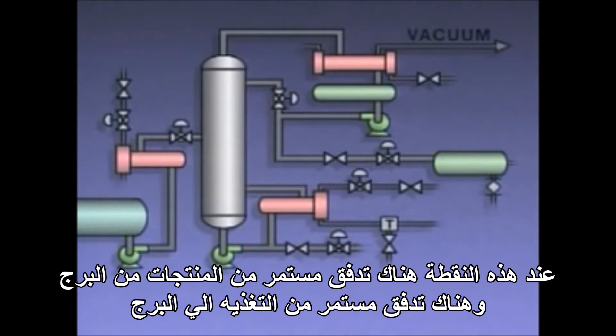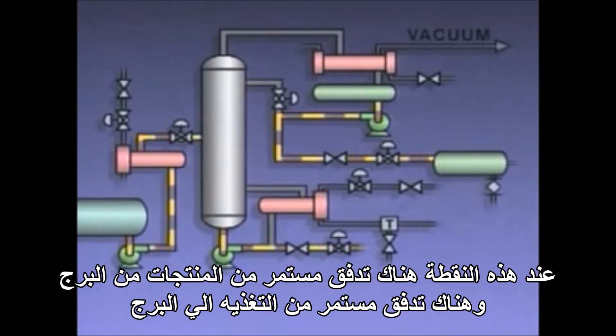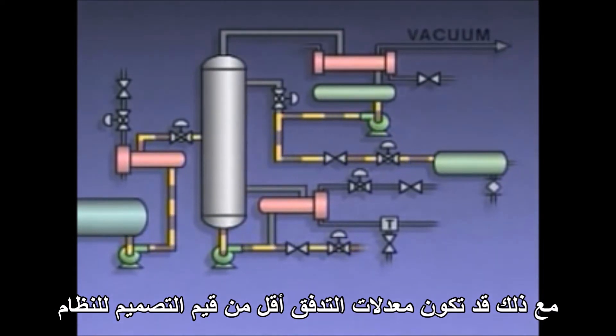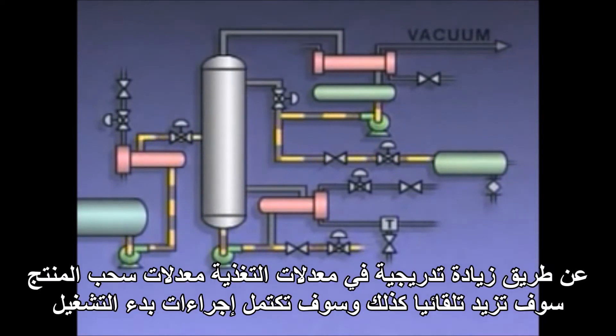At this point in the procedure, there's a continuous flow of product out of the column and a continuous flow of feed into the column. However, the rates of flow may be below the design values for the system. By gradually increasing the feed rate, the product takeoff rates will automatically increase as well, and the startup procedure will be complete.